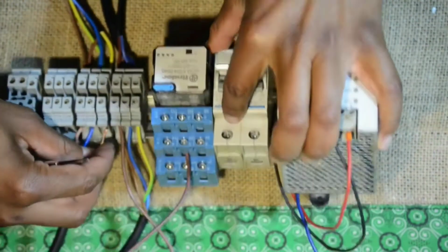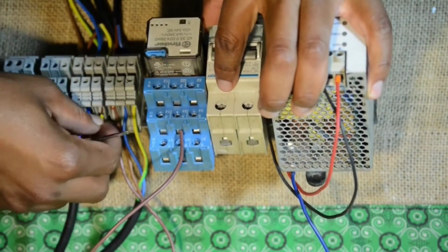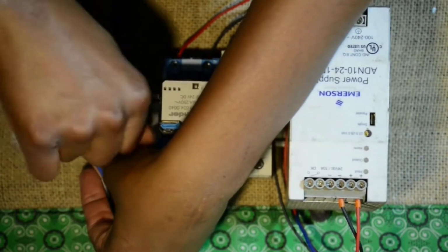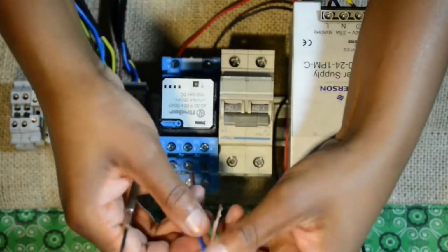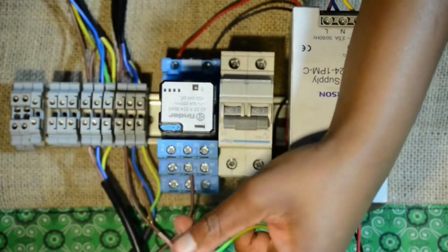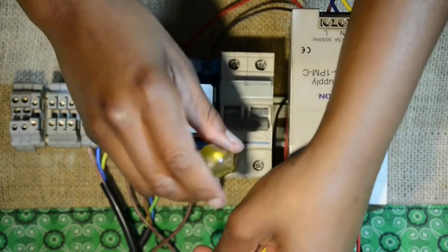And so the reason why we actually run this through a circuit breaker before taking it to the load is for the reason that if something is wrong with the circuit, or rather our load, if there is a short on our load, what's going to happen is that the mains is going to detect that fault and it's going to trip, right? And when the mains trips, automatically our backup is going to switch back on.